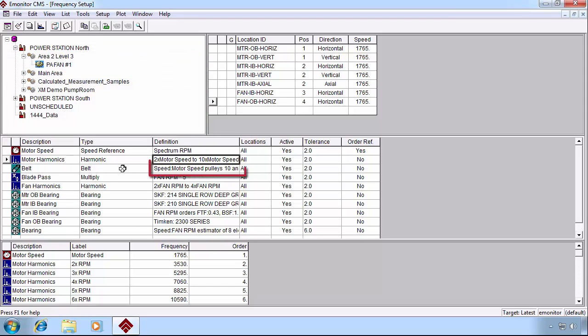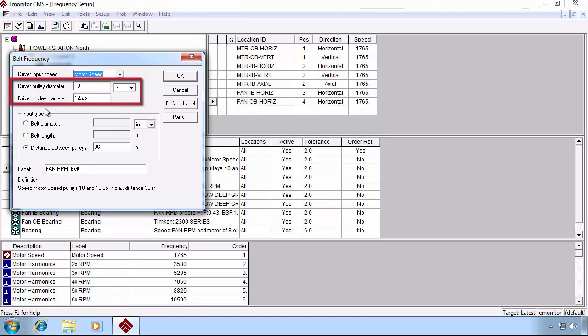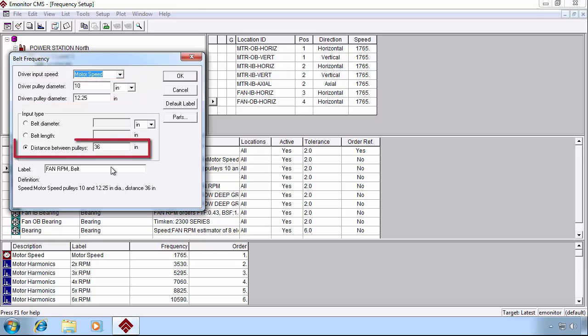Take a look at the belt frequency type. Again, we're adding it from the motor speed as our driver input. We give it the diameters of our driven and driver pulleys and the distance between those pulleys, and E-Monitor will automatically calculate the resulting output speed.